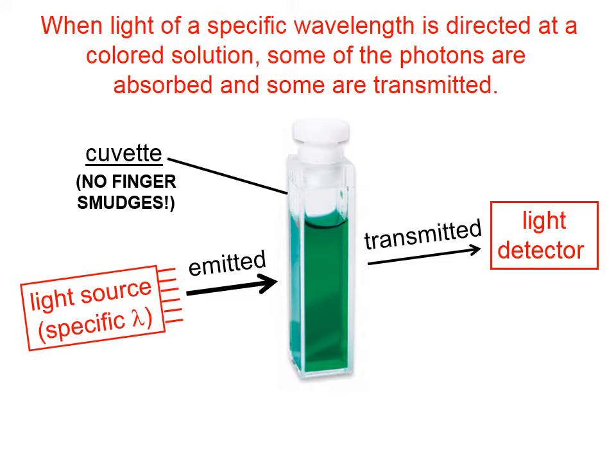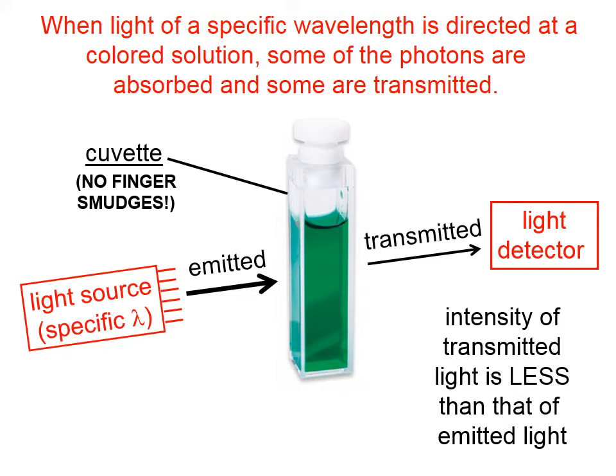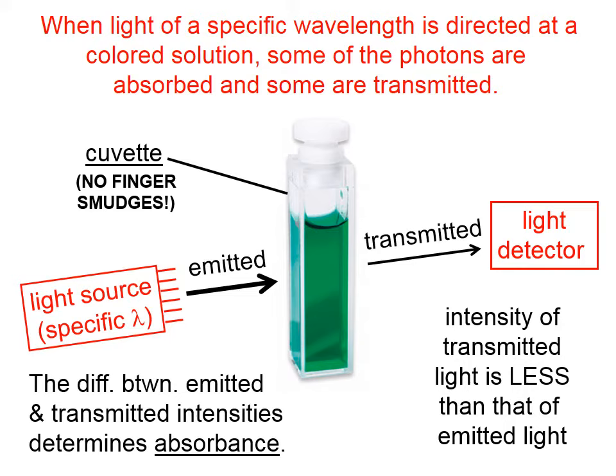The intensity of the transmitted light is less than that of the emitted light, and the more concentrated the solution is, the less light is transmitted. When we compare the emitted intensity with the transmitted intensity, we can determine the absorbance of this particular solution. If we have solutions of different concentration, we will get a different absorbance for each of those solutions.